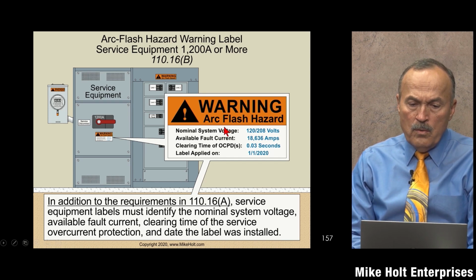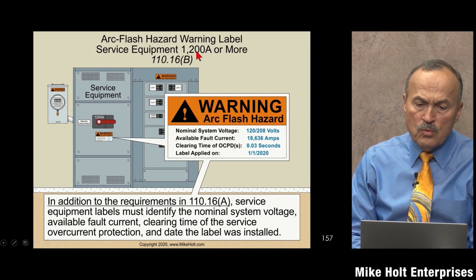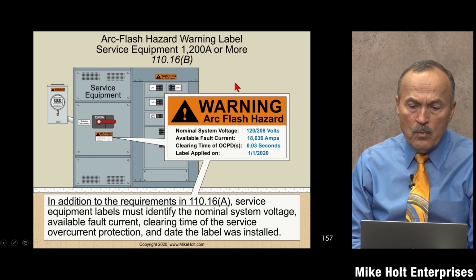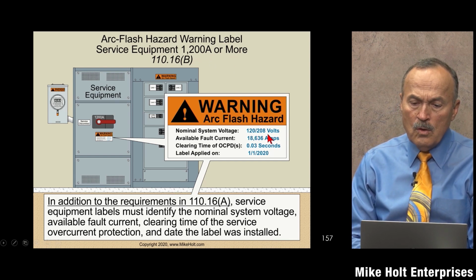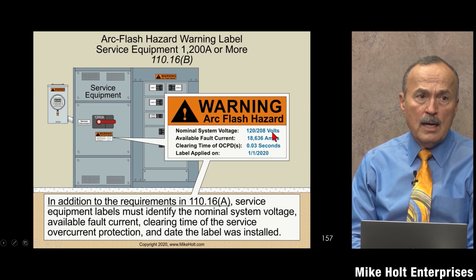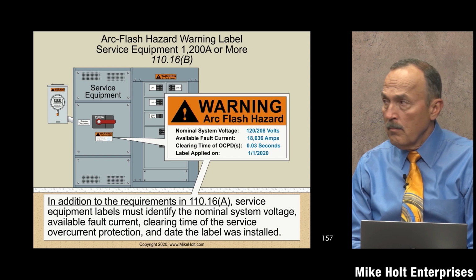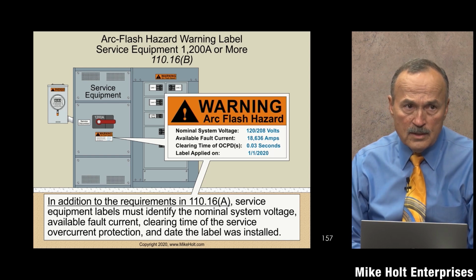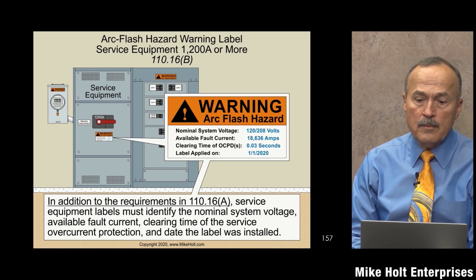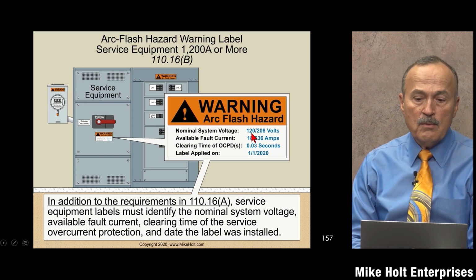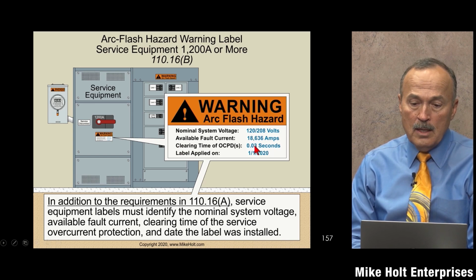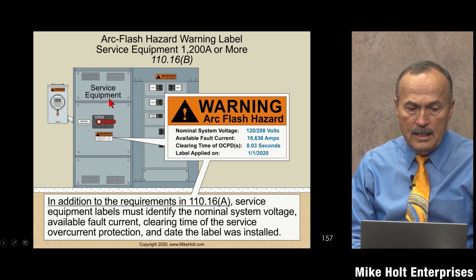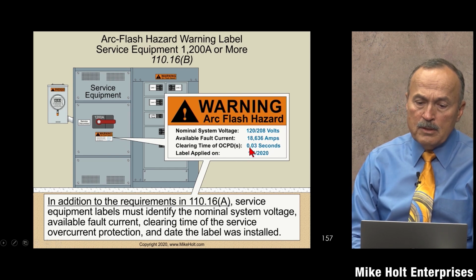So at service equipment, if it's rated 1200 amperes or more, we've got to put the system voltage, 120/208. In this case, we probably could change it to 208Y/120. Mike, well, let's change it to 208Y/120. I think that would be more appropriate. That would be the IEEE standard. That would indicate three-phase. And then this is the available fault current calculation, 18,636. That's on the line side. And then the clearing time was 0.03 seconds.